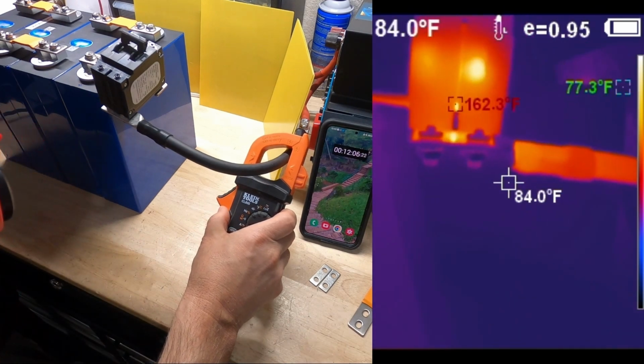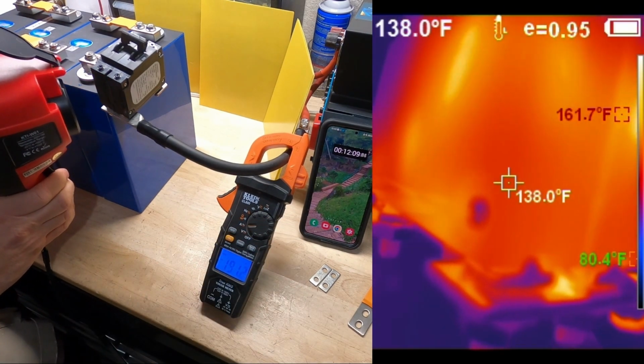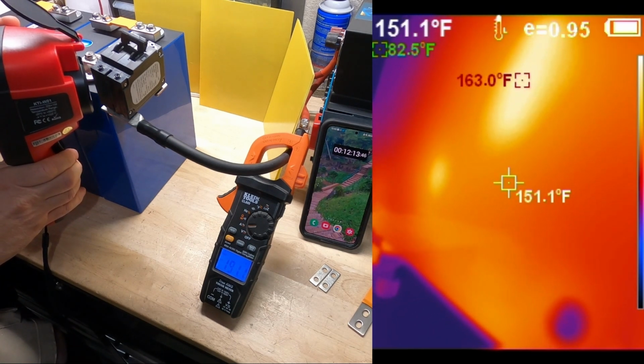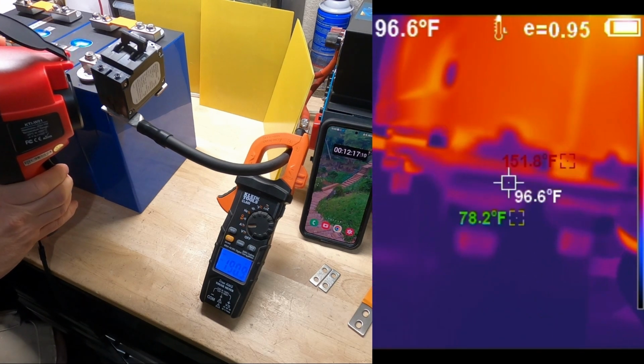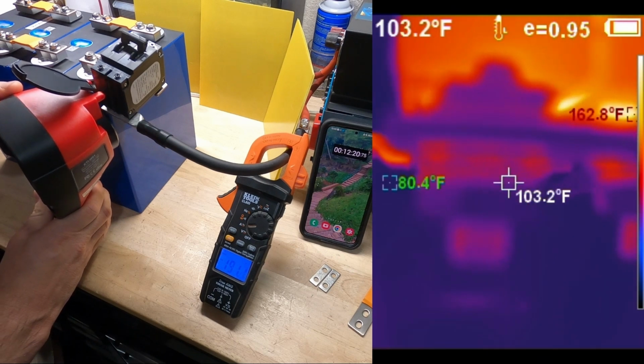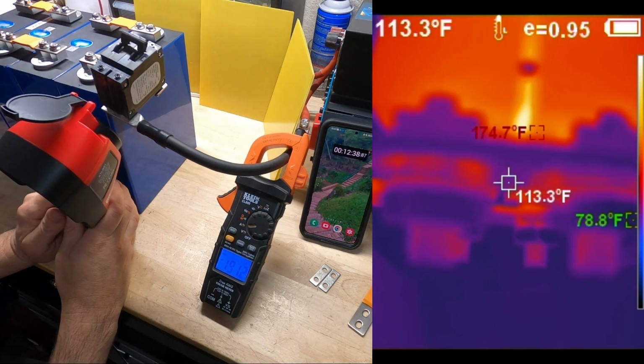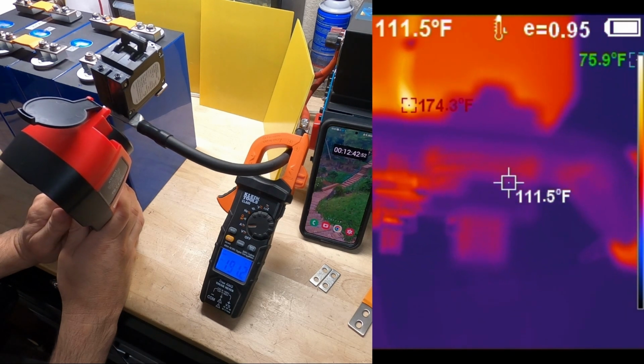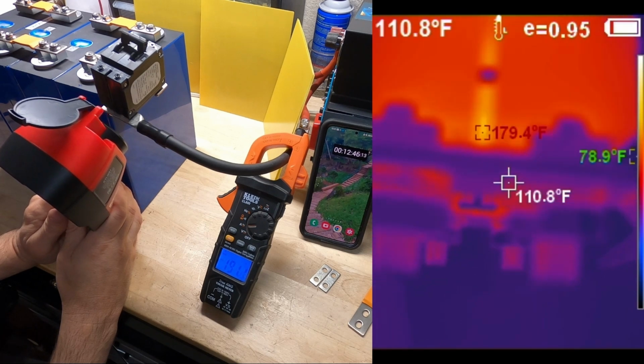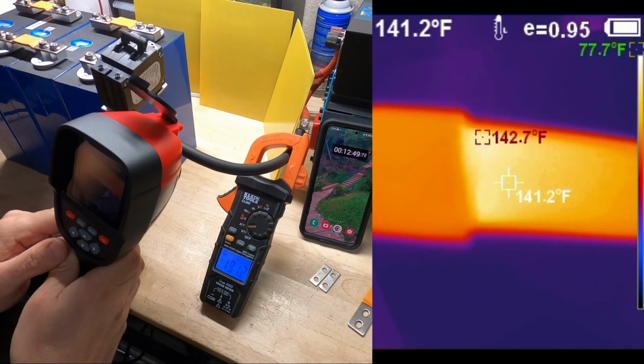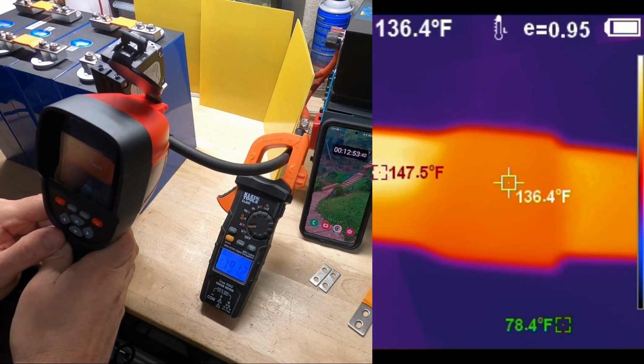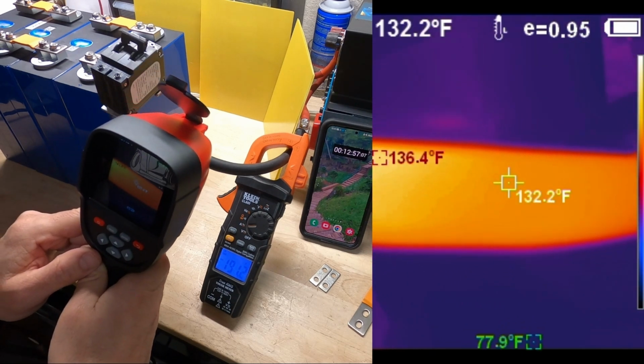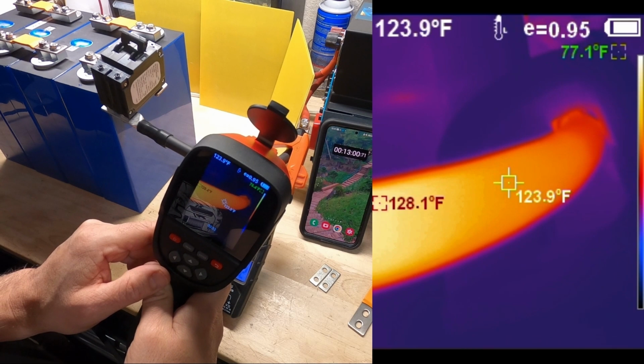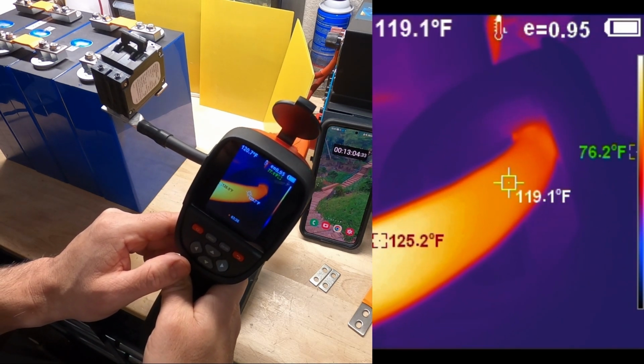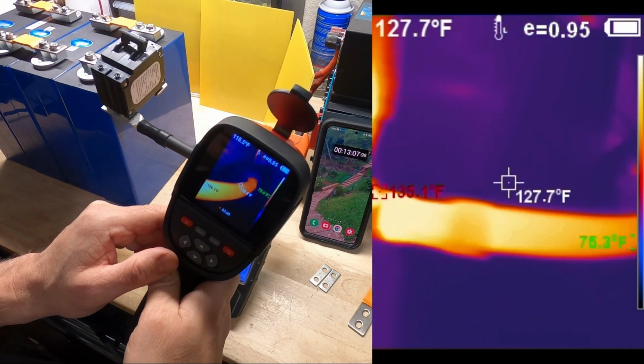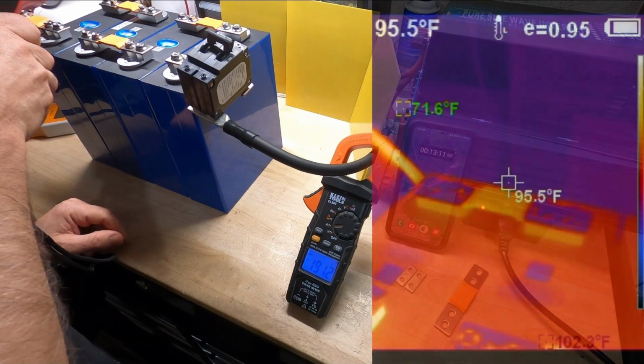Let's take a look at the breaker and cable. So per usual, the breaker internals are pretty hot, 160. Same temps we saw before, not surprised. But the contact terminal looks to be around 90 to 113, 120. And let's look at the cable. So of course near the connection it's going to be really hot. As you go down the cable, you're going to see it's cooler, 120, 130 max. The cable looks good to me. And these cell studs, these are really good. These are actually doing really well.